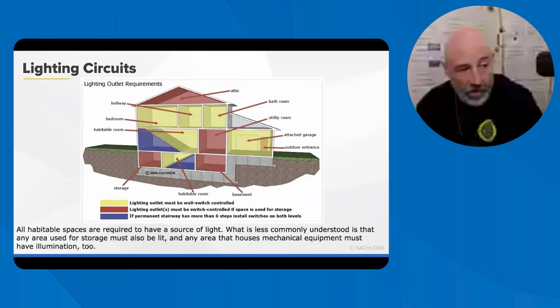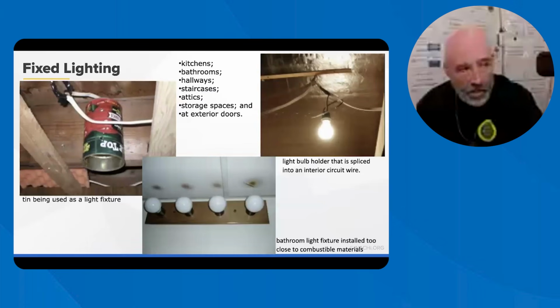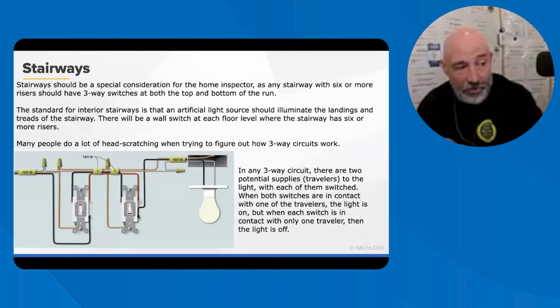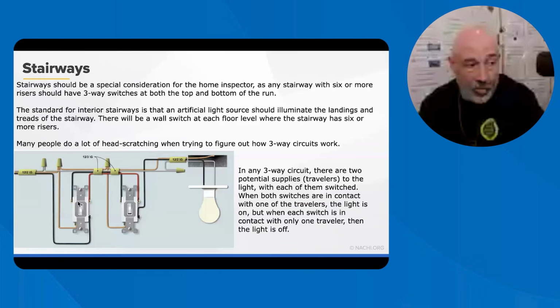Lighting: you want to make sure you have adequate lighting when you're going up and down the stairs and hallways. Make sure those three-way circuits are working properly. We don't want to see things like this. Make sure you're calling that stuff out, especially if you see burn marks. That's why you don't see them in bedrooms anymore. Here's how three-ways actually work. Take a screenshot of that if you want. I'll give you 5 seconds. Sorry, time's up. That's basically how they work.